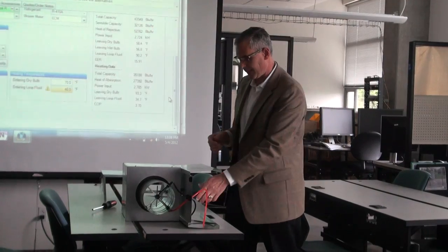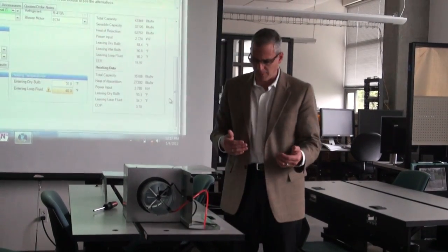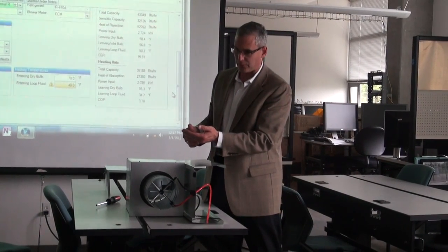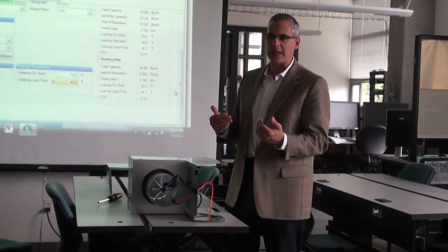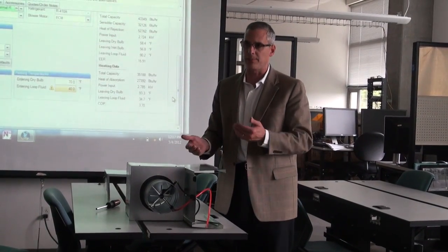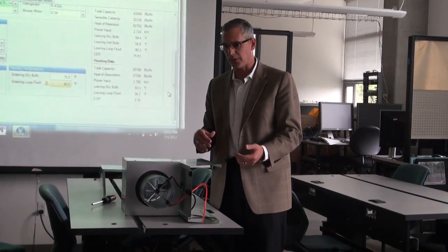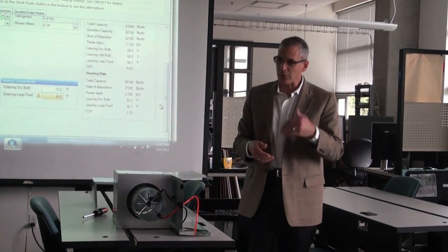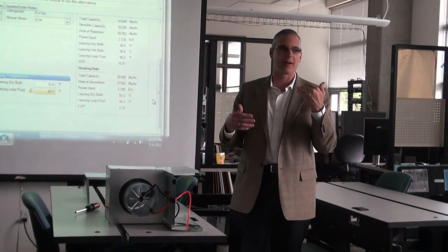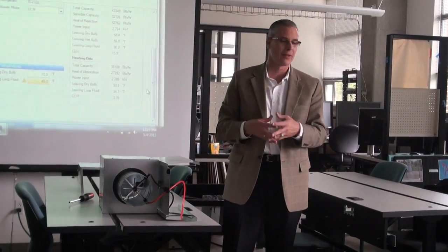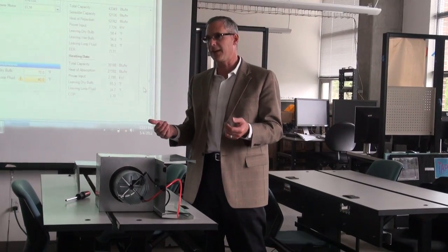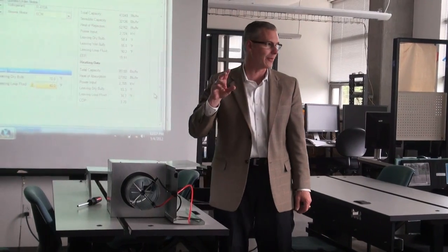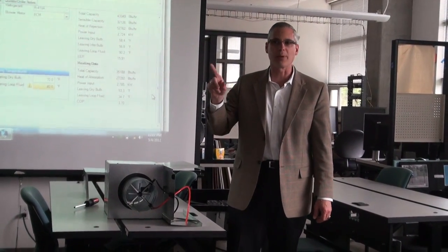Okay? And the other type is a parallel box where the fan is off the side, blowing this way, and it's only going to be sized for the plenum air and a heating load. So it's a smaller fan, and it only comes on for heating. And so you'll hear it modulate. And it was much more efficient than a series box, but it was noisy. Not in terms of its total noise, but in terms of an annoying change in sound. So it'd kick on. People would hear it.